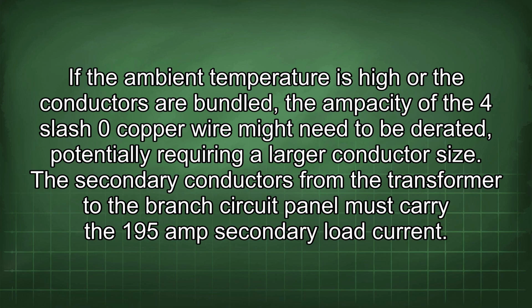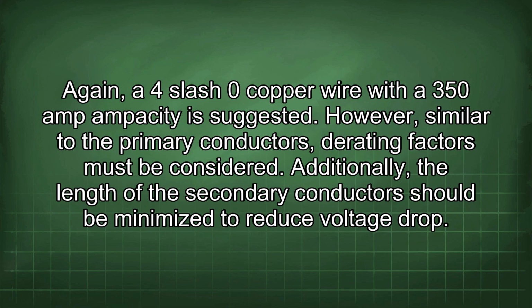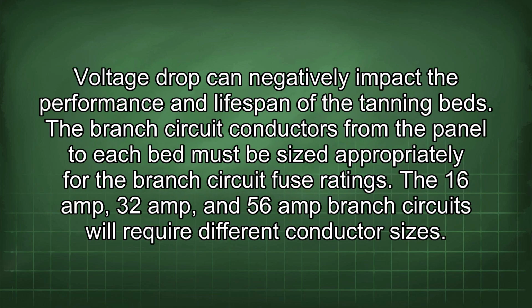The secondary conductors from the transformer to the branch circuit panel must carry the 195 amp secondary load current. Again, a 4/0 copper wire with a 350 amp ampacity is suggested. However, similar to the primary conductors, derating factors must be considered. Additionally, the length of the secondary conductors should be minimized to reduce voltage drop. Voltage drop can negatively impact the performance and lifespan of the tanning beds.